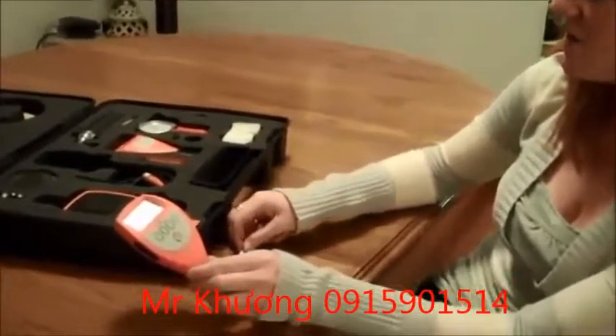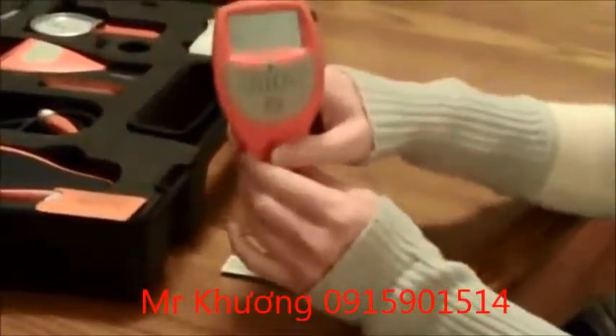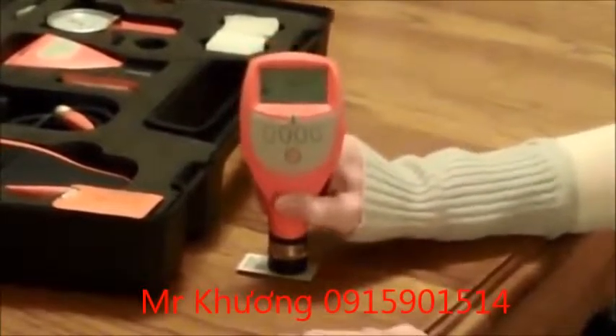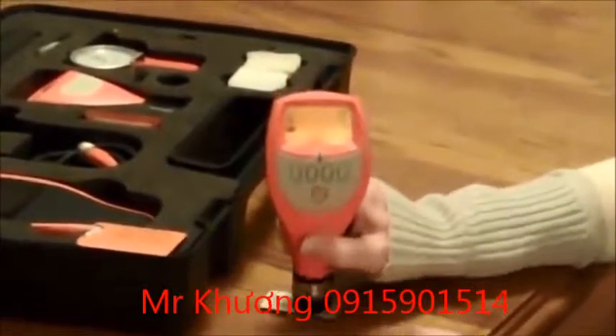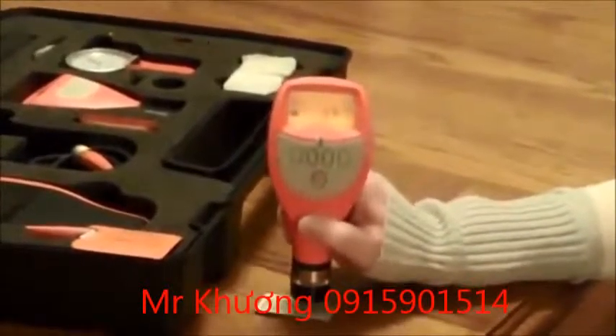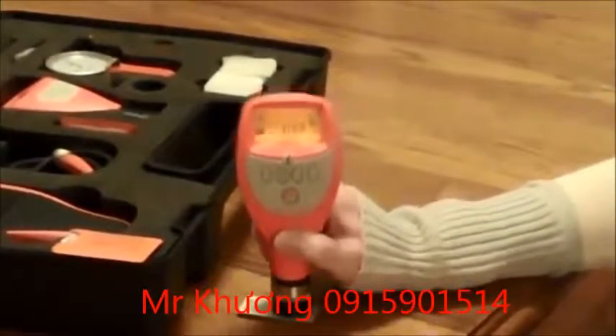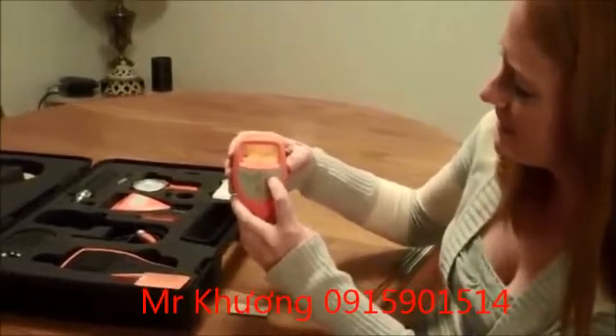Then it's going to ask you if you want to test your readings. Now you want to test your readings so that you make sure that your calibration is set correctly. So I'm again going to put the 9.9 shim onto the base and test it to make sure it's right around 9.9. Oh, first you have to press yes. 9.9, 9.9, 10.0, 10.0, 9.9. Then I can hit OK.